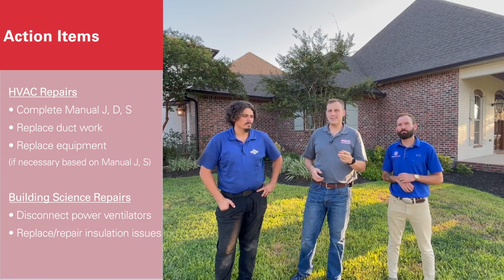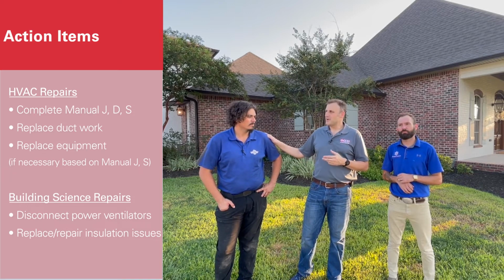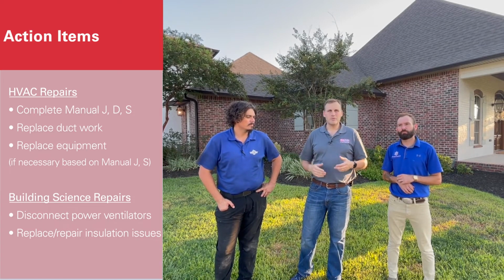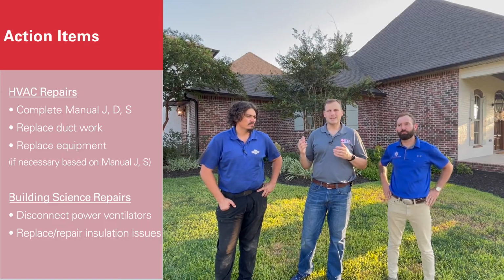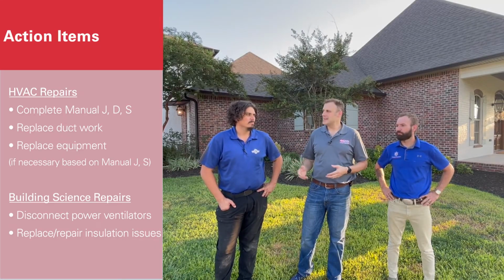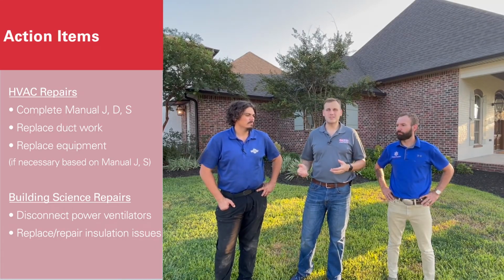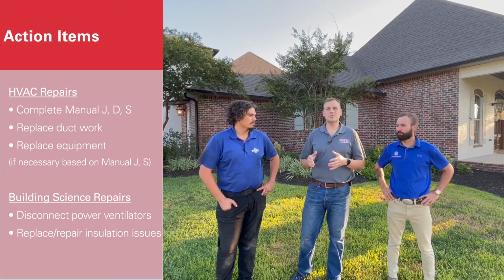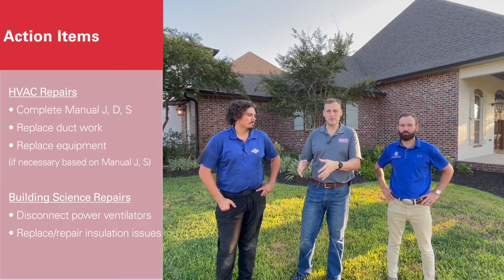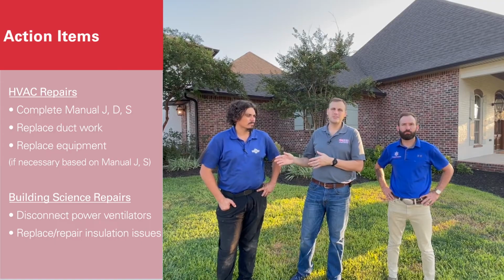Now, the second thing that Dustin did that we're going to classify in our building science is he went with the thermal camera and he started looking at the insulation in the walls, and he identified that we have some insulation issues, which are going to lead to individual comfort complaints per room, okay? Now, that is also building science driven.